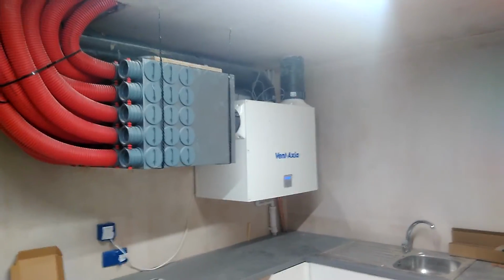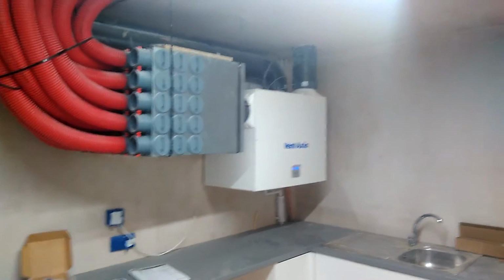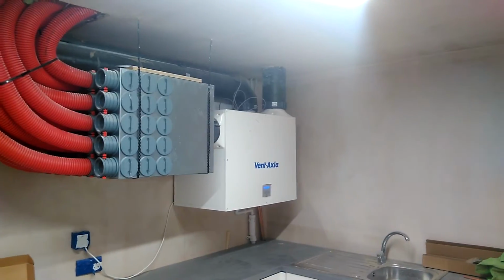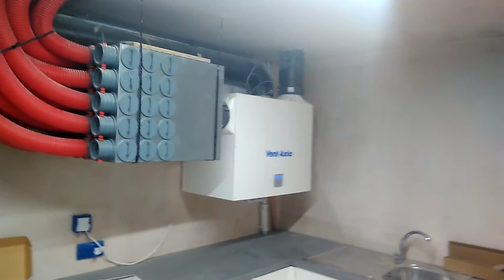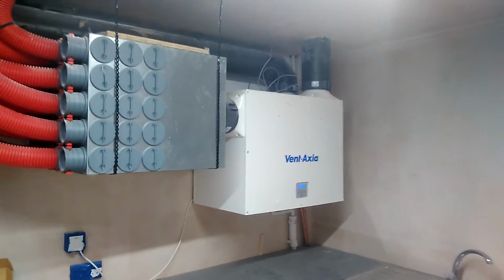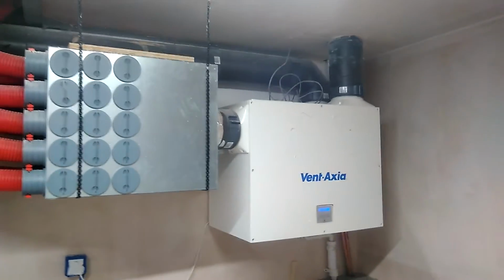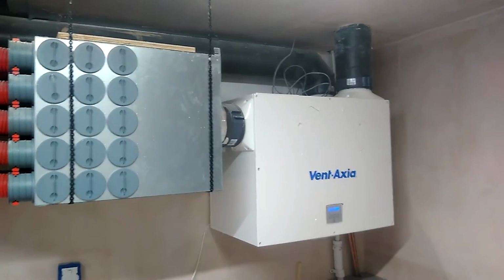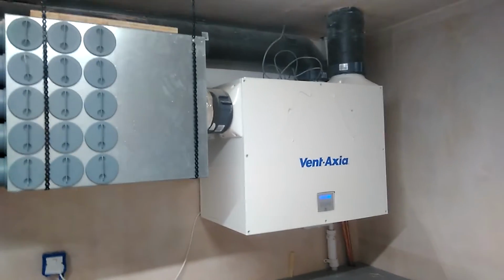Do you remember this machine we installed months ago? We're here to do second fix and commission. I've already commissioned the machine. It's working perfectly. It's balanced in all three modes: low mode, normal mode, and boost mode.